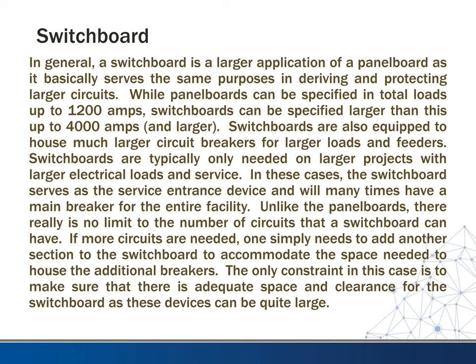Unlike the panel boards, there really is no limit to the number of circuits that a switchboard can have. If more circuits are needed, one simply needs to add another section to the switchboard to accommodate the space needed to house the additional breakers. The only constraint in this case is to make sure that there is adequate space and clearance for the switchboard, as these devices can be quite large.